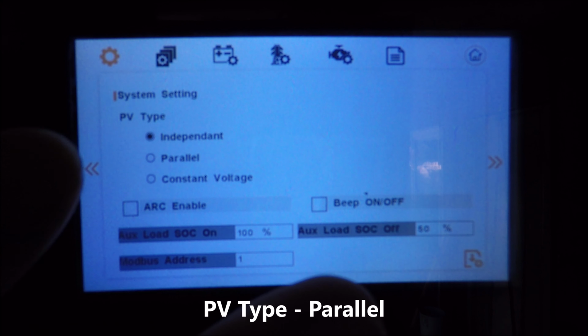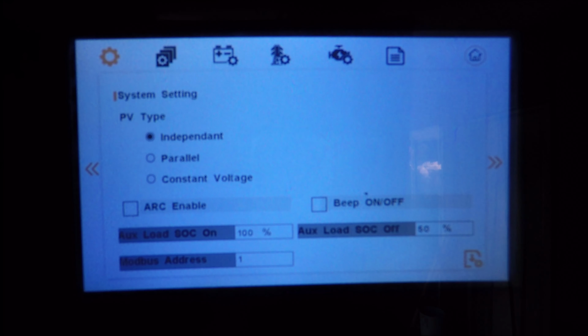You can use parallel. The parallel setting combines all MPPTs to act as one single MPPT controller. Now, you can do this if all of your panels are the same specifications, will not have any different shading, and they have an identical orientation. If all of those things are true, then you can combine them and you may get some additional efficiency out of the array. However, keep in mind that if you have any shading on any part of it, it will drop the voltage in the output for the entire array.